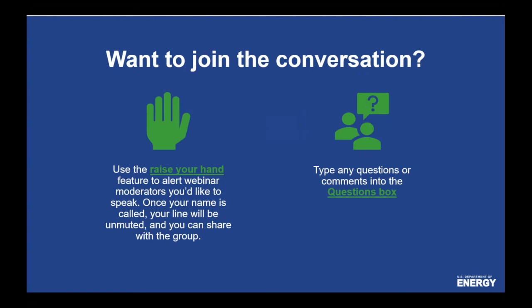Let me see here. Okay, so one question, and sorry folks, I'm trying to multitask and read these as they're coming in. One of them is a question about using VFDs to reduce the power factor, similar to downsizing oversized motors. So holistically, and I'll do a bit of a swag answer, the general consensus is yes, VFDs can be used to help mitigate the effects of power factor and help bring it more into unity to help your facility.